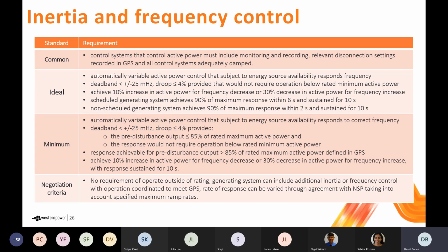For scheduled generators, you want to achieve 90% of the maximum response within 6 seconds and sustain it for 10. For non-scheduled generators, it's achieving 90% of the maximum response in a shorter period of time, that's 2 seconds, and sustain for 10 seconds. When we then look at the minimum performance standards, they're somewhat similar, but offer relaxations. So again, it's subject to energy source availability.